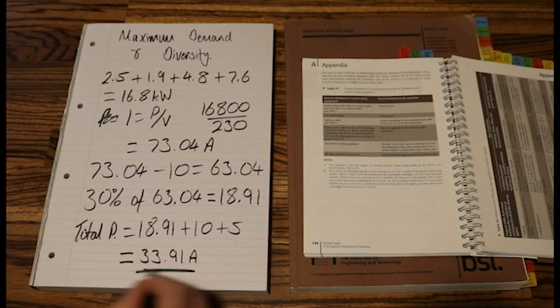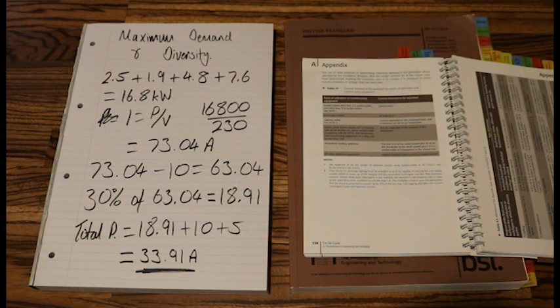And that is the total. So I would then use that for my, if you're doing a cable calculation, that would be my IB, and I would choose a cable that could carry that current, that just under 34 amps. And that is how we work out maximum demand and diversity on a simple cooker circuit.